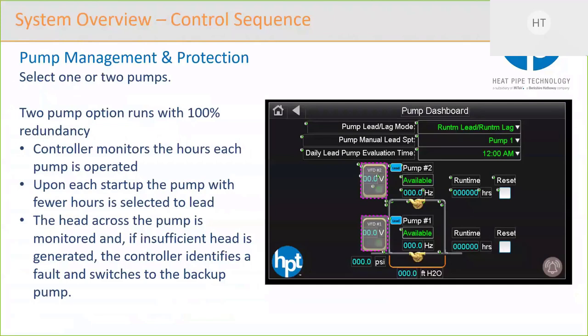The other protection we have is that the suction gauge pressure is being measured. The system will not run unless that gauge pressure is above a minimum threshold. The reason for that is to protect the pump from either running dry or cavitating because there wasn't sufficient head going into the system.